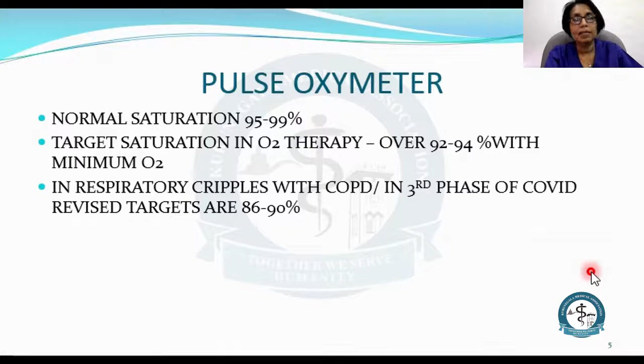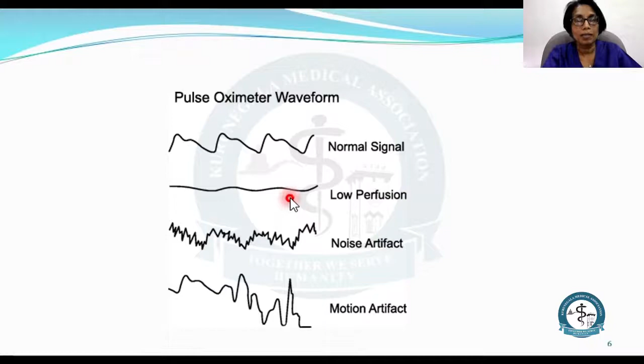So I said we have to ensure a good pulse oximeter waveform to get a correct reading. The first wave shows a normal pulse oximetric waveform. So anything other than this first waveform can give you erroneous readings. In that case, adjust the pulse oximeter probe so that you get a good signal and a correct reading.